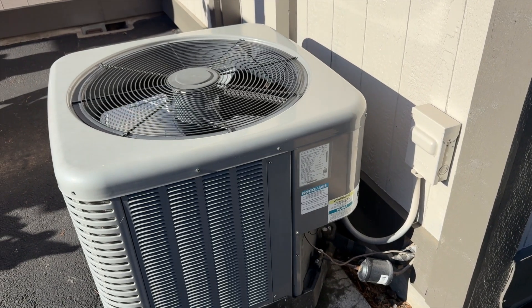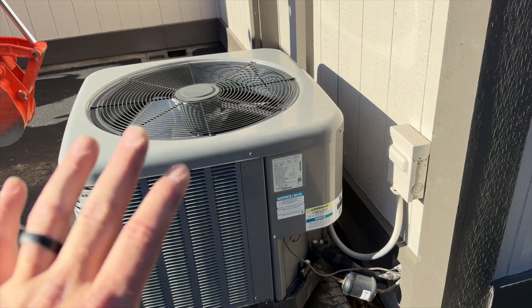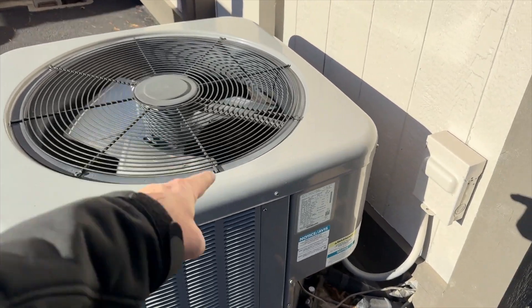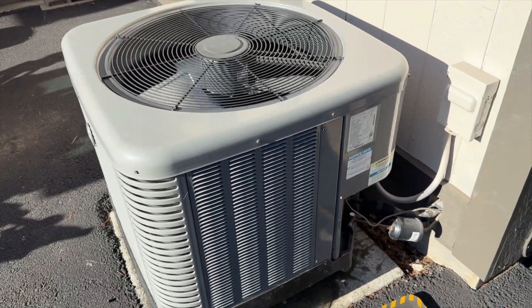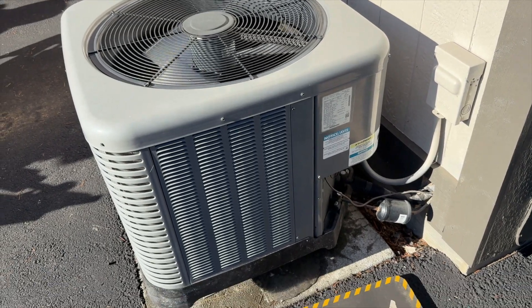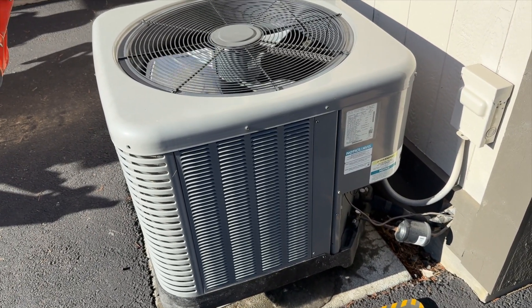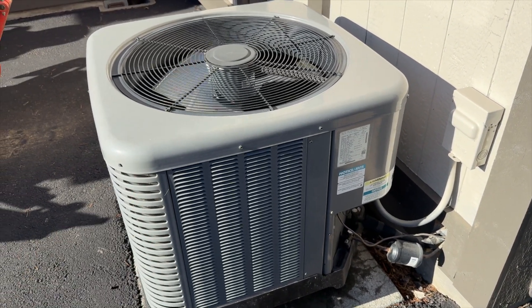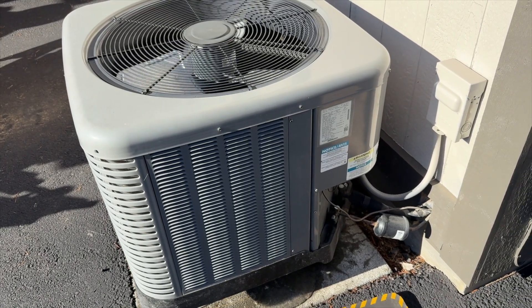She's all put back together. I'm calling for heat right now, just the heat pump — no more burning fuses. Everything seems to be good, so it looks like it was just that short on the high pressure or low pressure switch wire. Hopefully this helps you out on trying to hunt down a short. It's a very tedious process and everybody does it a little differently — this is just how I do it. Thanks for watching, make sure you like and subscribe.